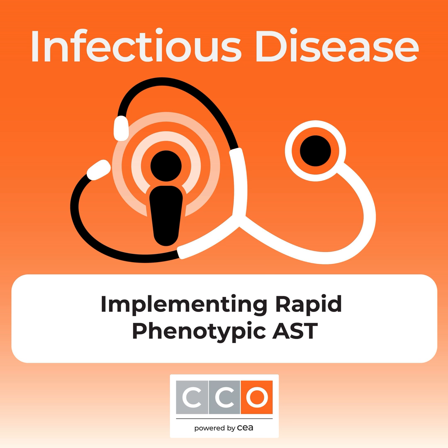We are used to automated AST platforms where we can validate new breakpoints, CLSI breakpoints, and make changes as users. So I think those are some limitations that some of these platforms have. Hopefully in the future, laboratories can have more open access to this type of software so we can validate ourselves. It could be a limitation, and it's important for you to keep that in consideration.